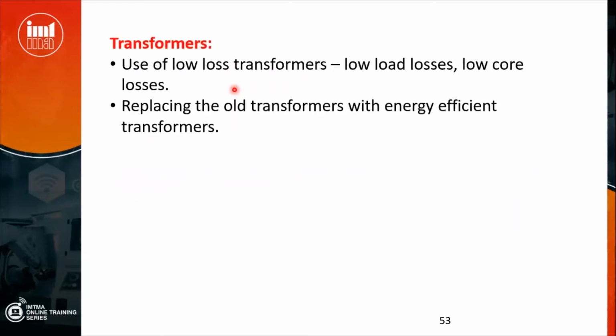Now coming to transformers. A transformer is stationary equipment, so comparatively the efficiency is much larger here. It goes up to 97%, 98%. So low loss transformers are available. In transformer design, depending on the flux density in which they are working, the thickness of the stampings of the core, and what type of wires they are using for the winding, efficiency and losses will be different. The core losses may be constant.